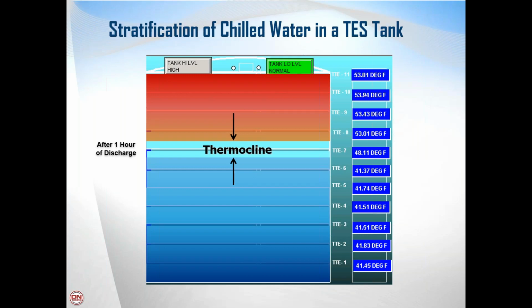And so that sensor can be their early warning system saying that there may be a leak somewhere out in the system. You may want to check that before you start draining all the water out of your chill water system. So those are the two types of sensors that are in the tank. There's the temperature sensor and the level sensor in the tank.